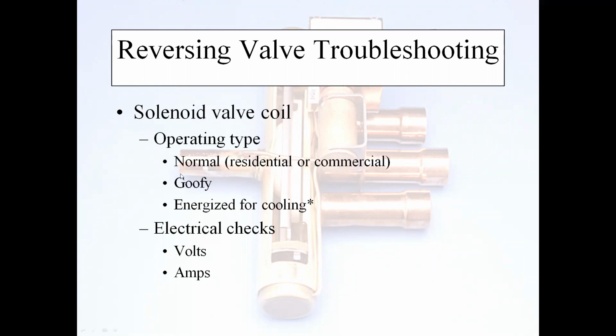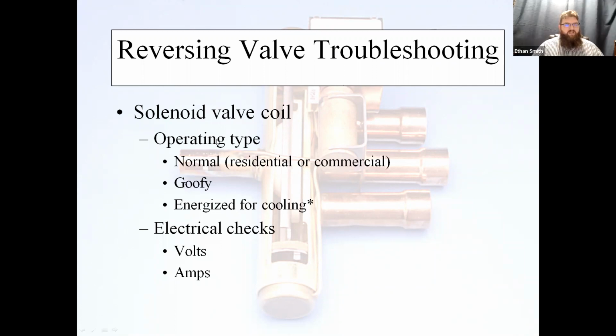One of the reasons you need to be able to figure out what kind of valve you've got is that you've got to know if it's supposed to be energized in the heating mode or in the cooling mode to diagnose it properly. If you go out there and there's no power to the reversing valve and you condemn the reversing valve, you may have just condemned a good reversing valve, because it may be de-energized in heating or it may be de-energized in cooling.